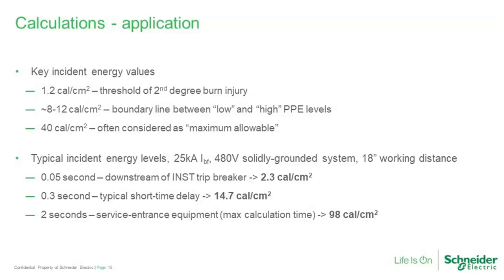So we're already into the level where we have some concerns to deal with. Short time: what if we're not tripping instantaneously? We're up at the next category, 0.3 seconds or 300 milliseconds, which is middle of the road for a short time delay. We may be pushing the capability of our standard PPE, having to get up into the more heavy-duty stuff, if you will.